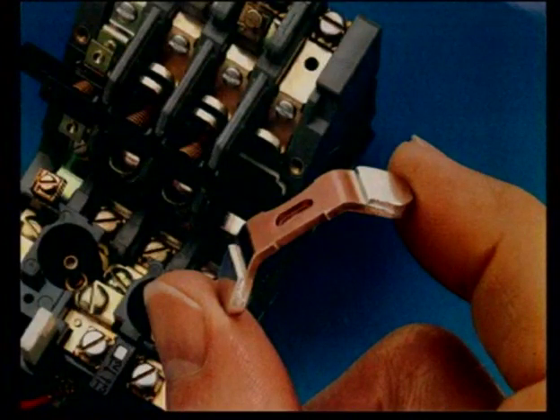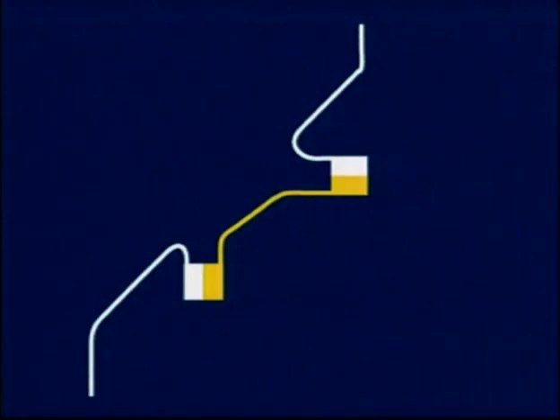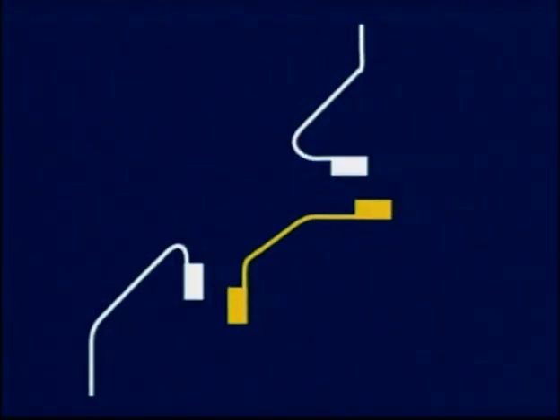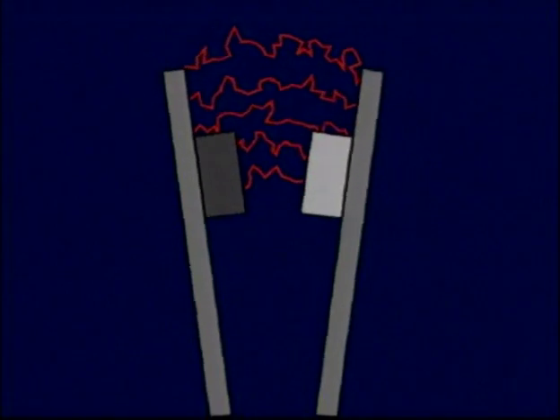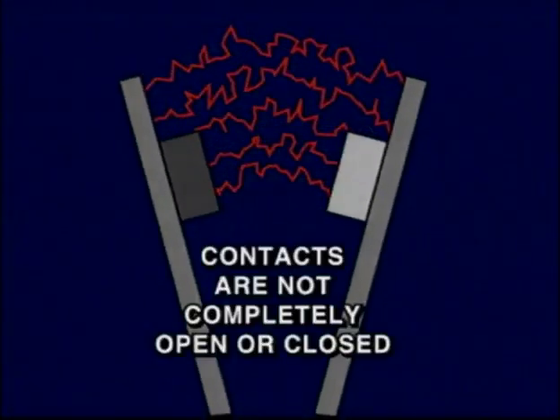Although the contacts and contactors are constructed of strong cadmium oxide and silver metals to fight corrosion and wear, they are still subject to arcing that is present during the opening and closing of the contacts. This electric arc is created because during the closing or opening of the contacts, there is a very short time in which the contacts are neither closed nor open, and the breaking of the current, which causes heat in the contacts, creates enough, so to speak, metal vapors between the gaps of the contacts, which are still trying to conduct current. This creates the arc.